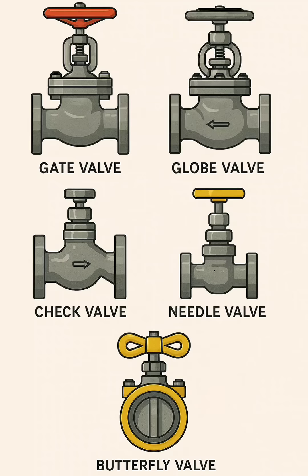Flow: Provides a short, straight flow path, but the disc is always in the flow, which creates some turbulence and pressure drop — more than a gate valve, less than a globe valve. Operation: Lightweight, compact, and can be operated manually or with an actuator. Use: Often used in large-diameter pipelines, ballast systems, and low-to-medium pressure service where space and weight savings are important.